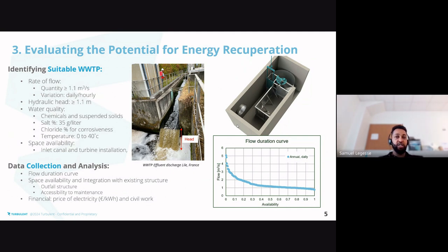As you can see in the picture, we want to clarify what we mean by head, because some customers measure it from the bottom of a canal, river, or in this case the outlet box, up to the top water level. But what we actually need as head to generate electricity is the elevation difference between water level and water level. On the right you can see our turbine installed in a metal basin in Versailles, France, which leads to the next parameter we consider when identifying a suitable site for turbine installation in a wastewater treatment plant.